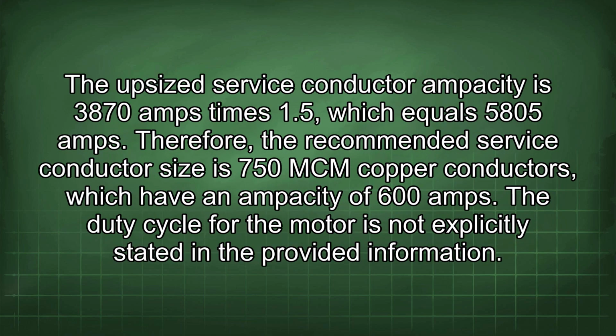The upsized service conductor ampacity is 3,870 amps times 1.5, which equals 5,805 amps. Therefore, the recommended service conductor size is 750 MCM copper conductors, which have an ampacity of 600 amps.